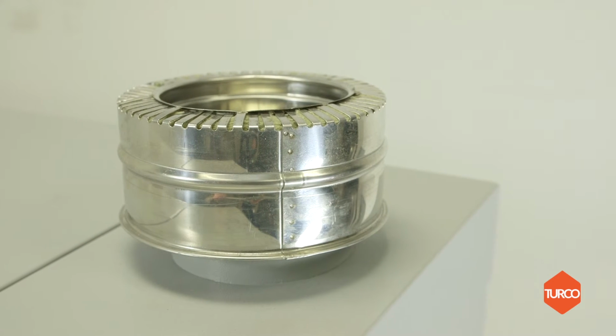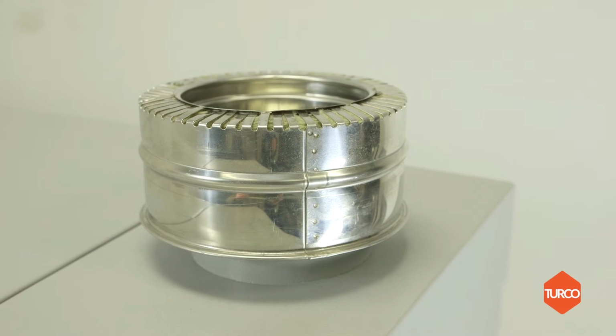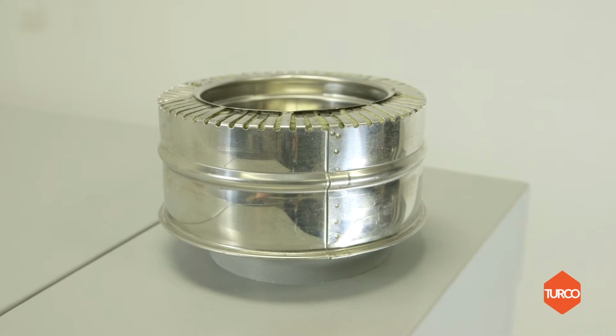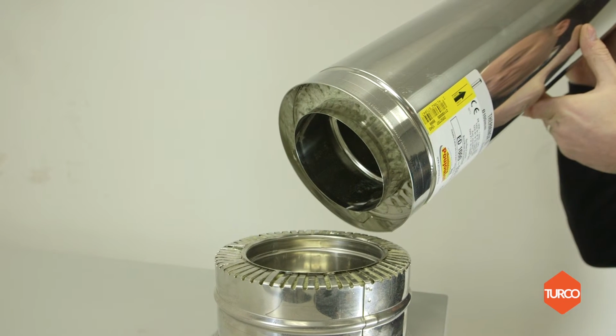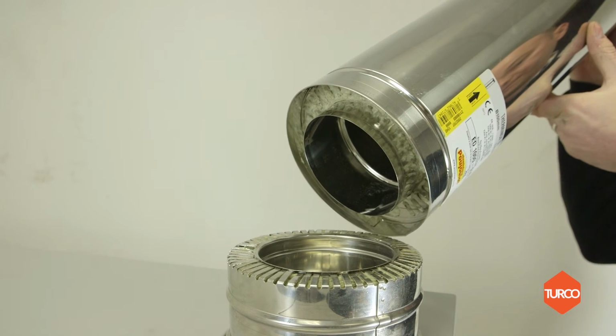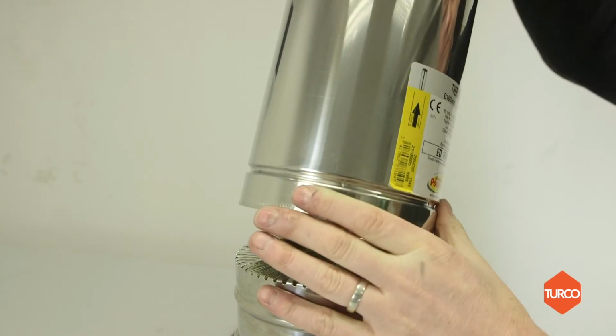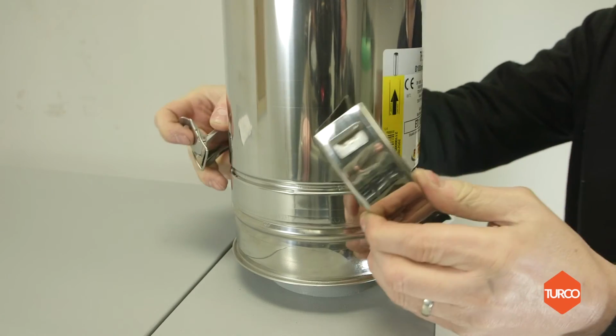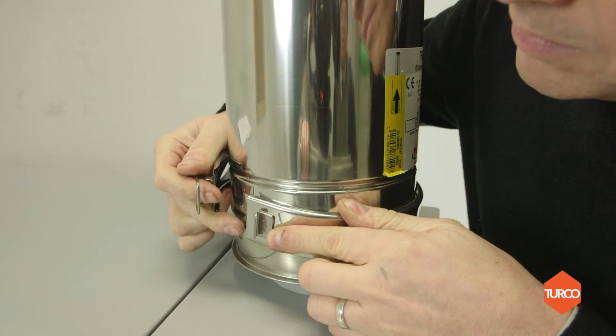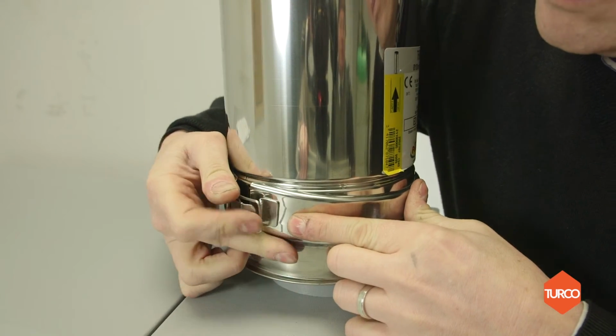Woodsman biomass boilers have an 80mm diameter transition pipe from the exhaust fan to the flue adapter. Woodsman boilers have been tested and approved with 4-inch 100mm twin-wall stainless steel insulated flue, so you'll need an 80/100 adapter. The installer can also choose to use a 5-inch 125mm flue.